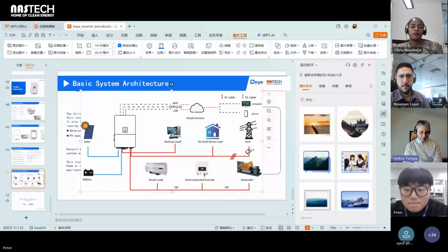Understood. And let's say we have a 125 kilowatt string inverter, one inverter just to make it easy. What will be the minimum size of the diesel generator to run this system? This actually depends on the load amount, so the load power. If you only have a small load, then the minimum generator, like a 10 kilowatt or 5 kilowatt generator, is fine, as long as it can provide the three-phase voltage for the inverter, then the inverter can start to produce. But if your load is a very big amount, like 100 kilowatt, then your generator at least has to cover all your load in case there is no PV.